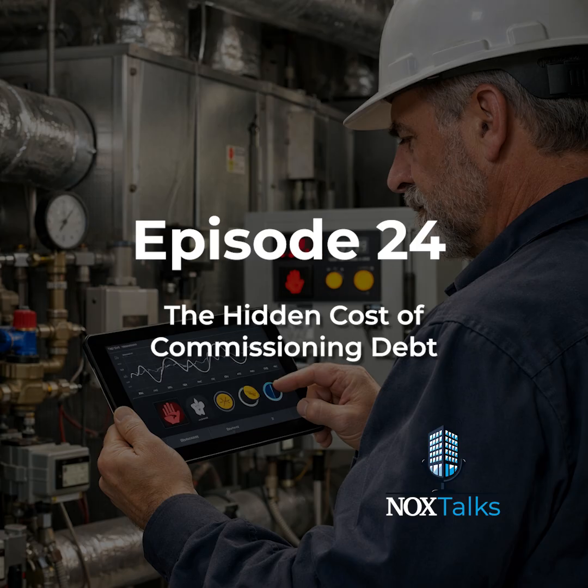So here are the moves I'd make first. Build a 90-day post-handover tuning backlog and rank every item by energy impact, complaint volume, and override count. Start with the air handlers and VAVs, because that's where a lot of the hidden fighting lives. Verify the sequence in the field, not just on paper. ASHRAE Guideline 11 exists for a reason. And budget for seasonal retuning, because TAB plus startup is not the same thing as commissioning complete in July, October, and January.